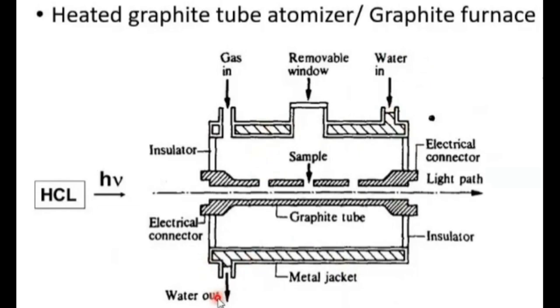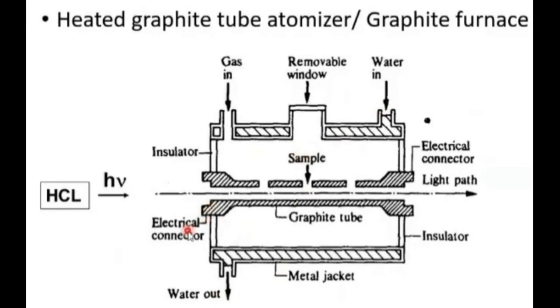The graphite tube is surrounded by a metal jacket through which water passes — used for cooling so the instrument does not overheat from outside. There are electrical connections on each side. Between the water jacket and the graphite tube there is an insulating separation forming a chamber. The window is removable so that the sample can be introduced, after which the entire process starts.